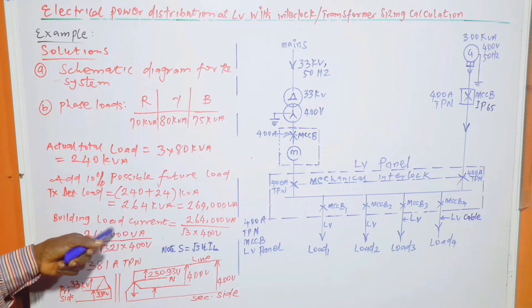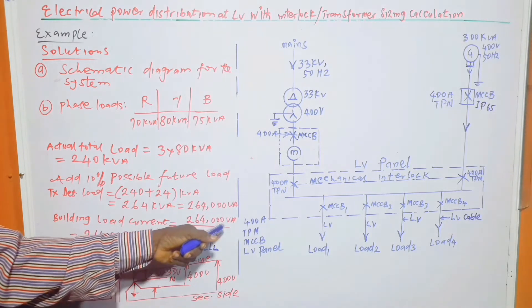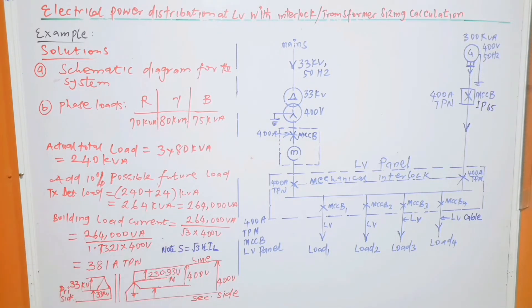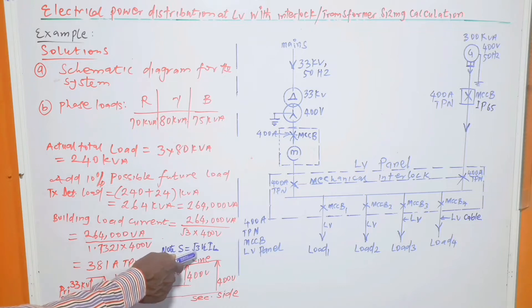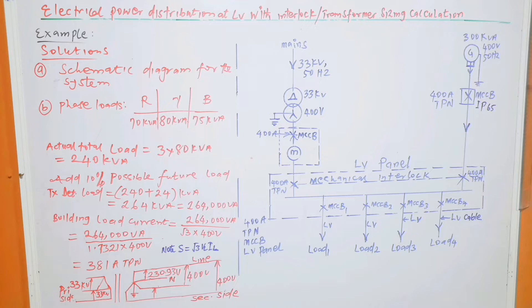Then we can move further to calculate the line current, the building load current, which is equal to 264,000 VA divided by root 3 times 400 V. From this formula, the apparent power is equal to root 3 times V line times I line, from which we calculate the I line to be equal to 381 ampere three-phase with neutral. In this case, it doesn't mean that the neutral current is 381, we are just saying that we have three phases plus neutral. It is the line current, which is equal to the phase current in this situation.